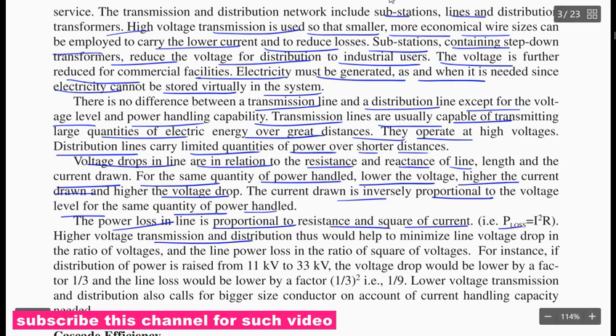Higher voltage transmission and distribution thus help to minimize the line voltage drop in the ratio of the voltage, because when the voltage is higher, the current is lower and the power loss is lower. The line power loss is in the ratio of the square of the voltage. For instance, if the distribution voltage is raised from 11 kV to 33 kV, the voltage drop should be lower by a fraction of 1 by 3, and line losses should be lower by 1 by 3 whole squared, that is 1 by 9. Lower voltage transmission and distribution also call for bigger size conductors on account of the current handling capacity needed.